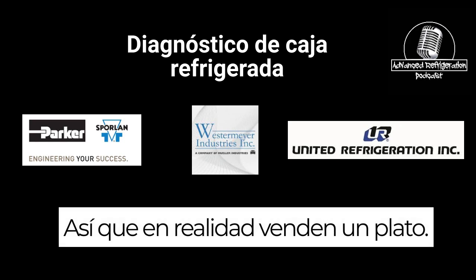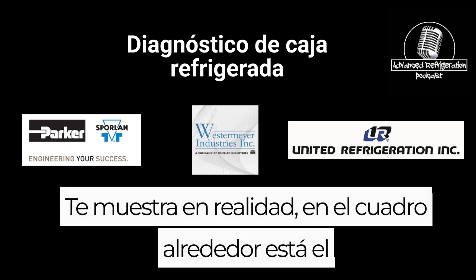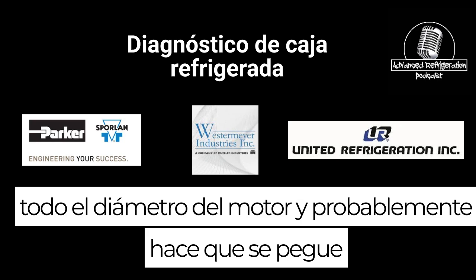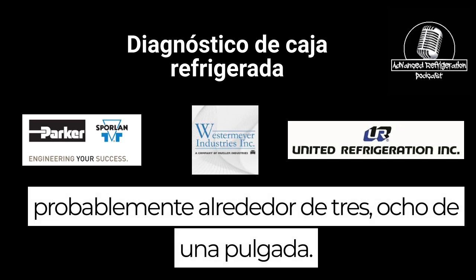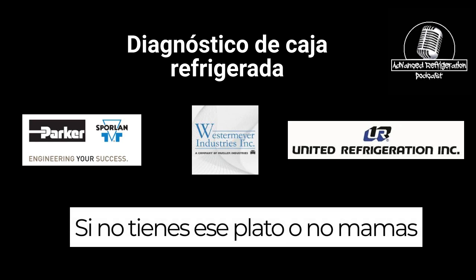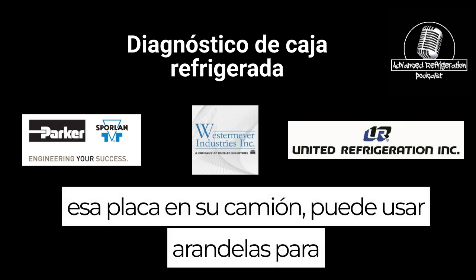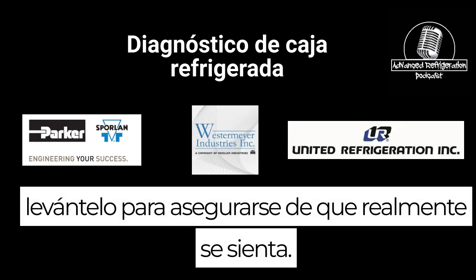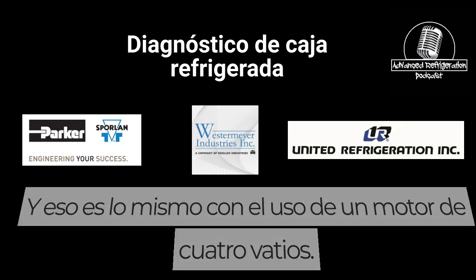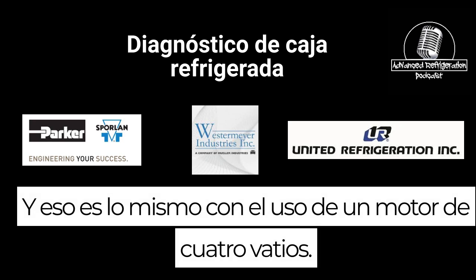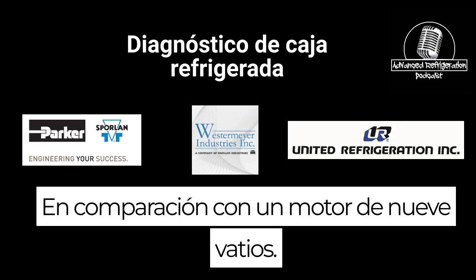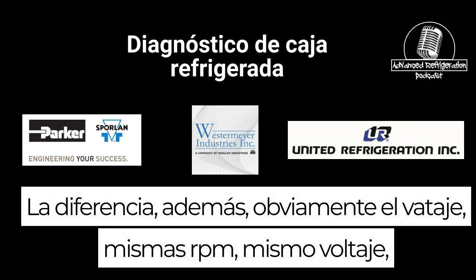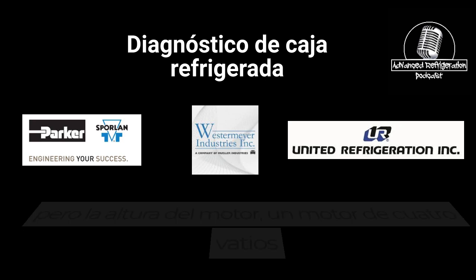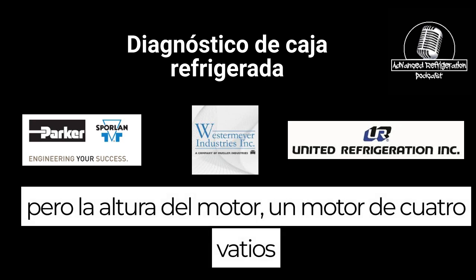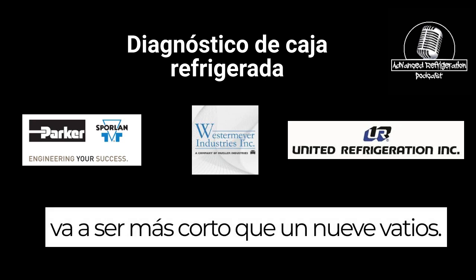So they actually sell a plate that goes on the back. It shows you on the box. It's around the whole diameter of the motor, and probably makes it stick up about 3/8 of an inch. If you don't stock that plate on your truck, you can use washers to raise it up to make sure it sits right. And that goes the same with using a 4-watt motor versus a 9-watt motor. The difference, besides obviously the wattage, same RPM, same voltage, is the height of the motor. A 4-watt motor is going to be shorter than a 9-watt.